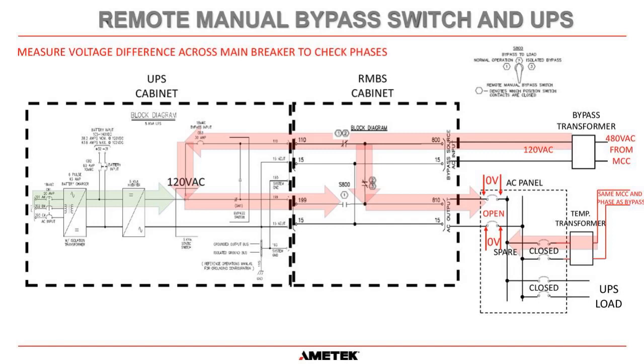Then we do what we did earlier on this input breaker, the backfeed breaker. We're going to do the same checks on the main breaker now. We're going to check we have 120 volts line to neutral. And then we are going to check across the contacts of this breaker because it's open and we want to see 0 volts. As I mentioned earlier, it could be as high as 10 volts, but we want to make sure that it is a steady voltage and that it's not more than 10 volts. Okay, so we've done our checks. Everything looks good. The next step is to close this main AC breaker.